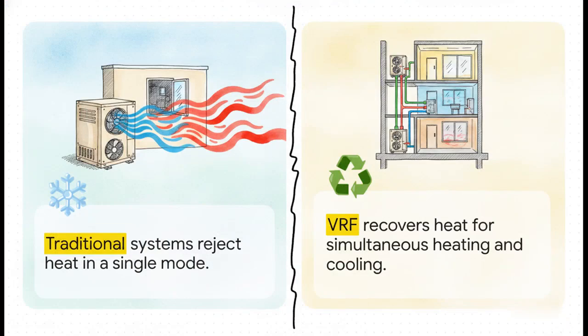Traditional heat pumps are honestly a bit brute force. They reject heat entirely and operate in a single mode, so the whole building is either heating or cooling. But a three-pipe VRF, or variable refrigerant flow system, operates with surgical efficiency. By utilizing a dedicated liquid line, a hot gas line, and a suction line, along with inverter drives, it can provide simultaneous heating and cooling to different zones in the exact same building. Instead of just dumping wasted heat outside, it recovers it and redirects it precisely to where it's needed. It's a massive leap forward.